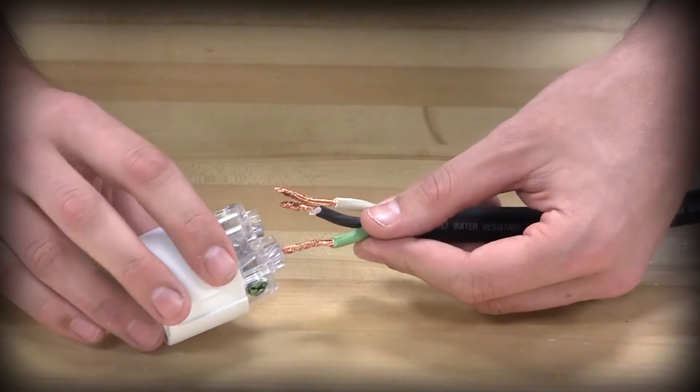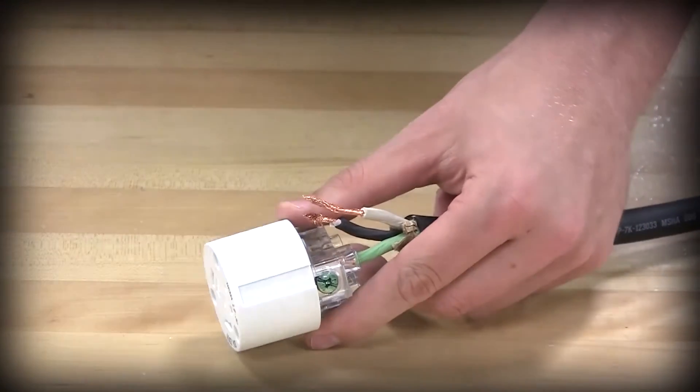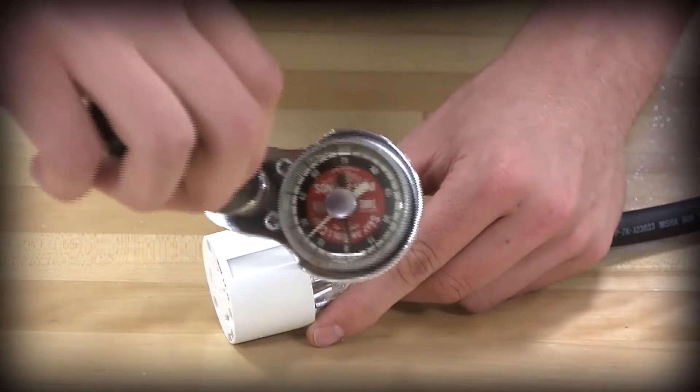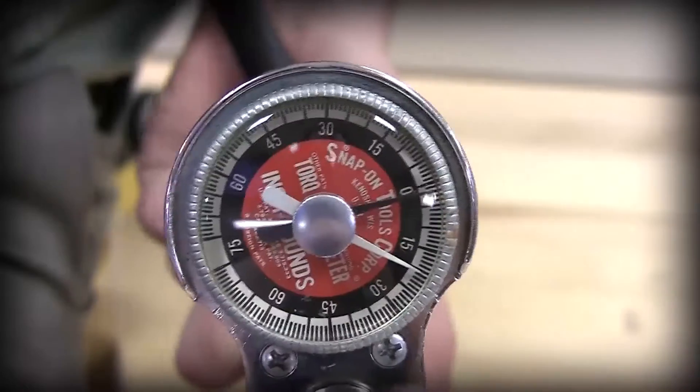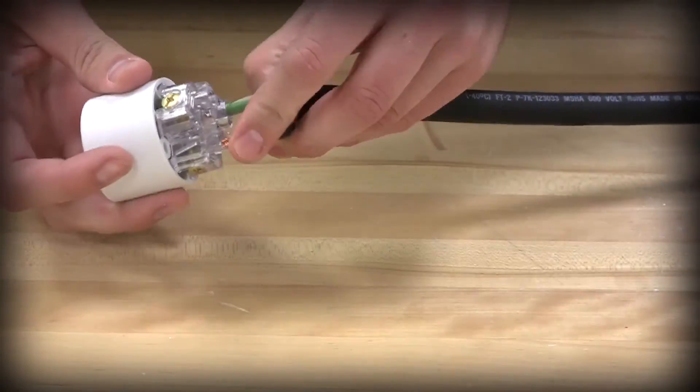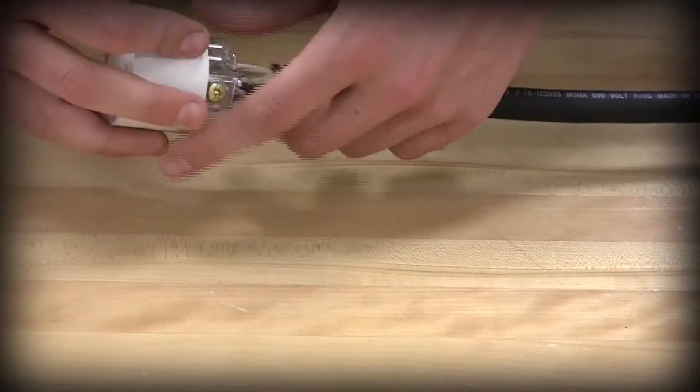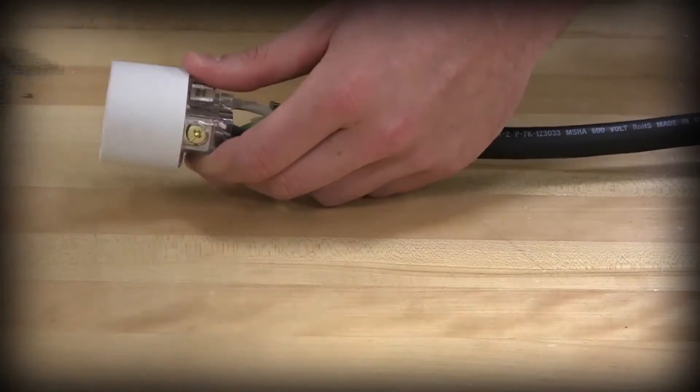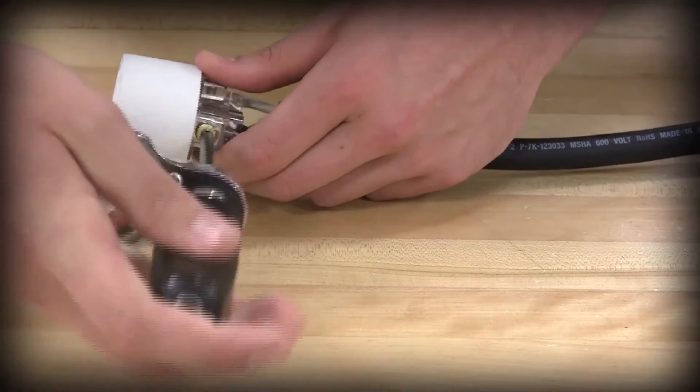Insert the stripped conductors into the individual wiring pockets and tighten each terminal screw as wire is inserted using 15 to 20 inch pounds of torque. The green screw is for the green ground conductor while the silver screw is for the neutral white conductor if it is present. The brass screw goes into the black conductor.